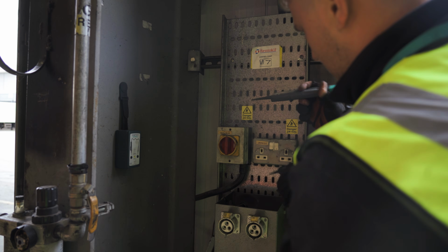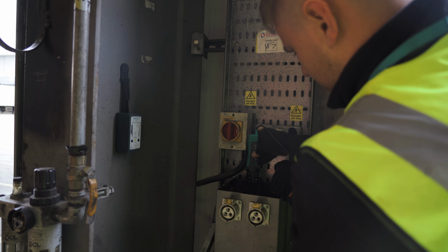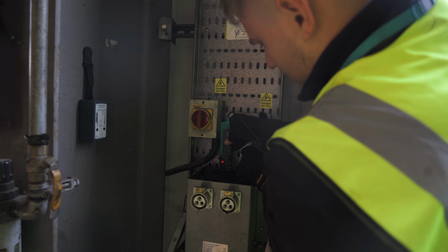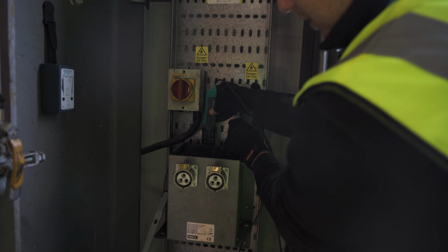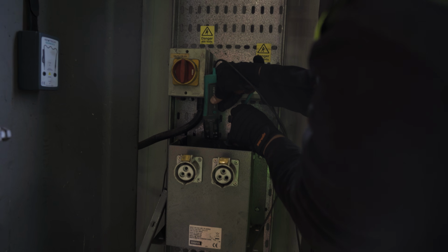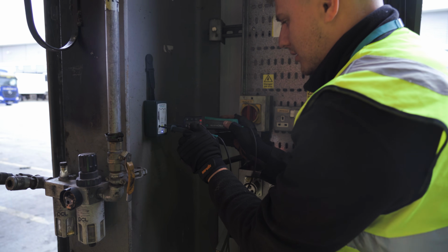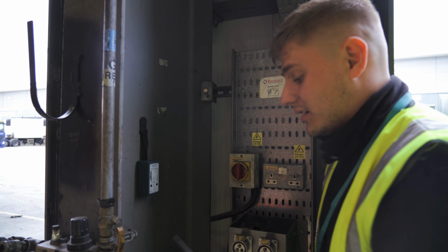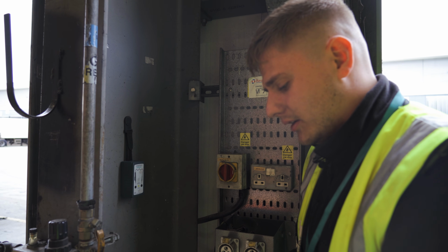Lovely job. Now I'm just going to test between live and earth, neutral and earth, and then neutral and live - and we are all dead. I'm going to jump back on these, prove the testers again, and that is us safely isolated.